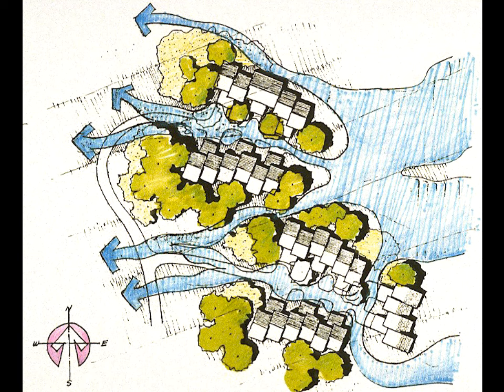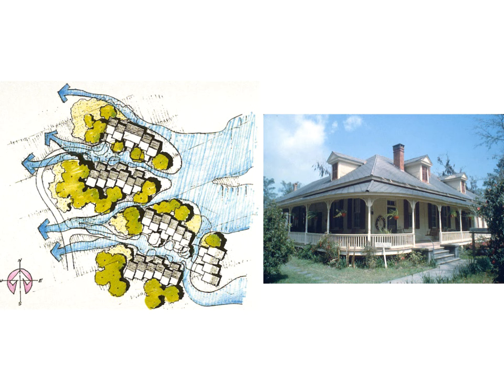The courtyard or shared space between groups of buildings is open, allowing air to move in through one end and exit out the other. This shows a rotated organization relative to wind orientation. With a rotated organization, you get positive pressure on two windward sides and negative pressure on the other two. Facing the opening directly toward the wind gives positive pressure on one side but negative on three, requiring inlet sizes to work with just one orientation. The rotated organization gives more wind access to more buildings and surfaces.